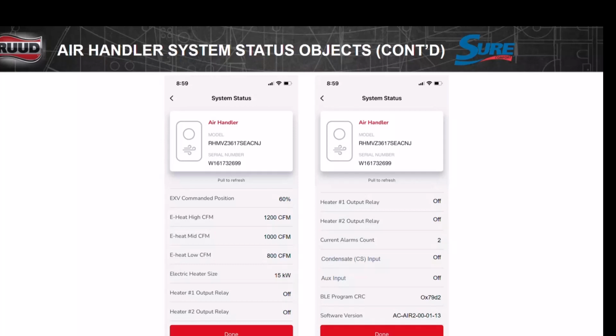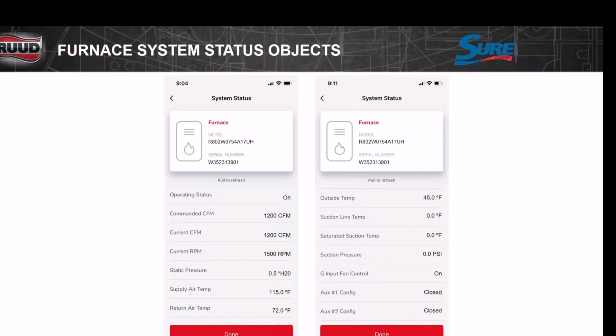If we're having some goofy things happening here, I'm going to want to know what software we're running on that air handler board. I want to know what software we're running outside, software we're running on the thermostat, just so we can see if maybe we didn't have a bug in that version, right? And I have the capability to come out and reprogram these boards if we had to. Most of the time we just tell you to change it if it was a problem in there. But if I'm on the job and I have my stuff with me, I can reprogram it and it wouldn't be a problem. Furnaces are the same way.